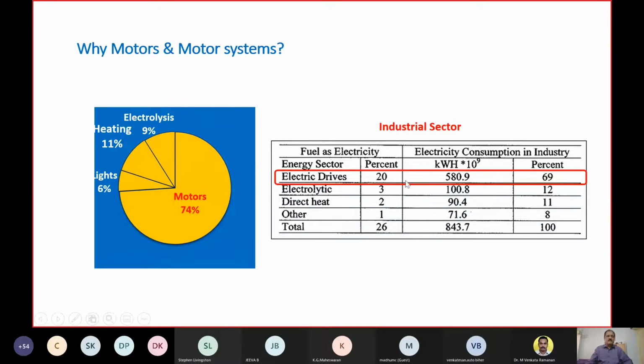And I have another graph on the left-hand side where motors contribute 74% of the total energy consumed in normal industries. So we'll have to talk about both the industry applications and the specific applications in thermal power stations for auxiliary power consumption, for our understanding of the topic. As you know, heating, electrolysis, and lights or IT loads contribute approximately 12 plus 11, 23 plus 8, 31. Approximately 31% of the balance requirements in the industries are met through these processes: heating, induction heating, electrolysis, and IT and lighting loads. So therefore, the motor becomes the single largest implement through which the highest energy efficiency is accounted.